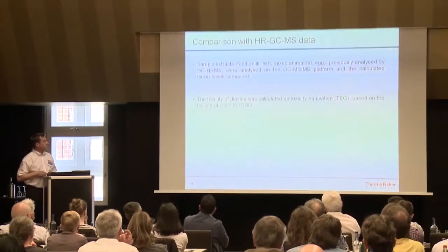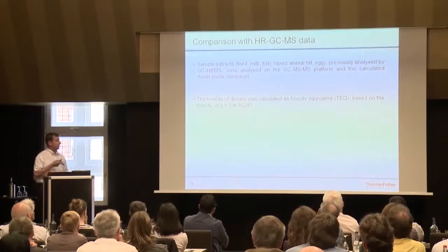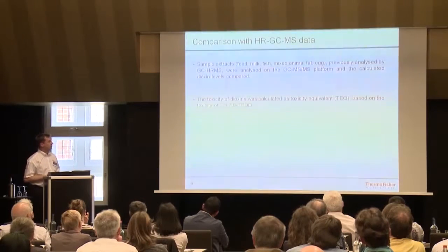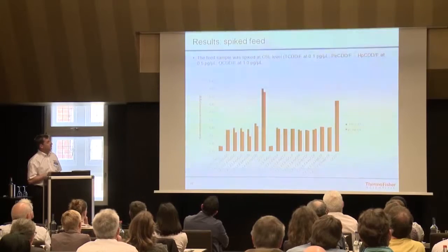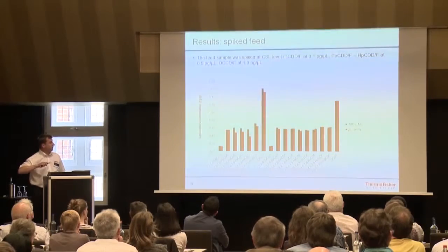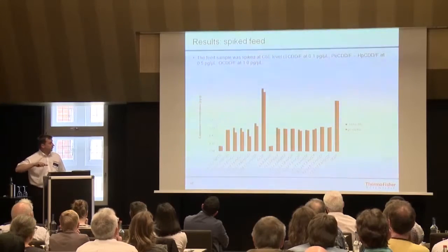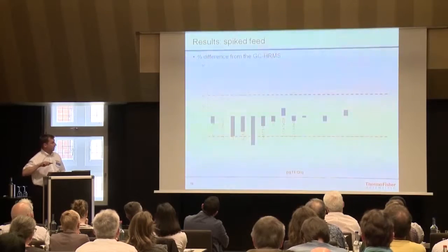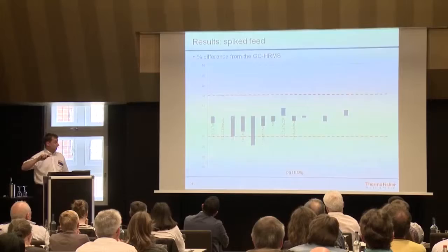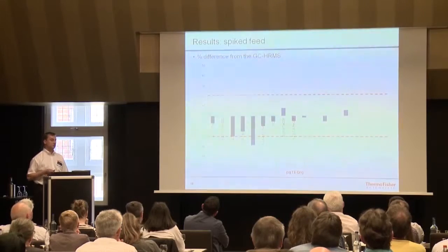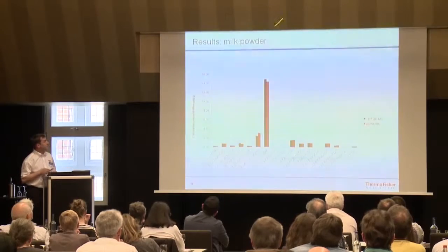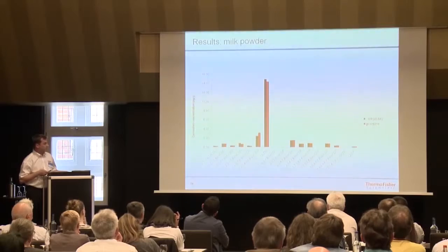For routine use, we tested the performance of our GC-MS/MS against the high-resolution sector instruments using samples kindly provided by Alex and Esteban. What you see here is a spiked feed sample — in red is the GC-MS/MS result, concentration in picograms per gram, and the high-resolution data alongside. On a congener basis, we are almost for all compounds within 20%. Another example for milk powder shows very good agreement between the two systems.